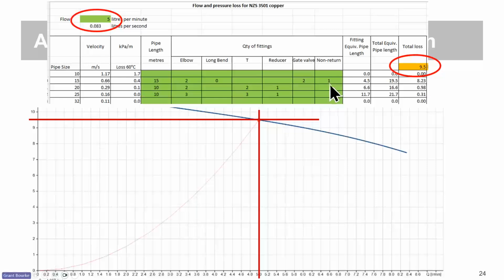Just a word about the non-return. These pumps are pretty small. If you use spring type non-returns with big buffy springs in them, the pump may struggle to get an initial open of that spring type non-return. So use a spring type non-return with only a very light spring, or maybe a swing check valve in that ring main non-return, so that the pump's not going to be unable to open it and nothing happens, and a valve either side of the pump.